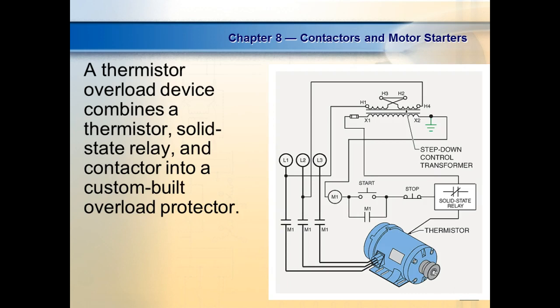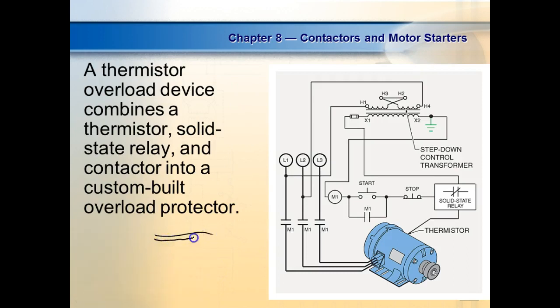So a lot of them have the bimetallic, we call them bimetallic strips. What it is, it's two pieces of metal. And they have different what we call coefficients. All metals expand when you heat them, and they contract when you cool them, right? You understand that? Well, different metals expand and contract at different rates. If we take two metals and strap them together, then one of them expands faster than the other, and we actually bond them together, then when you heat it up, this strip would literally curl up. And that's what a bimetallic strip does.